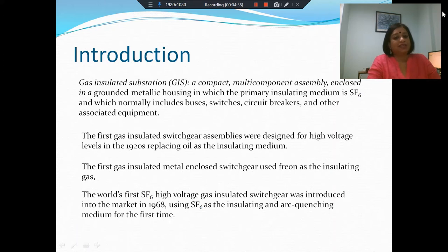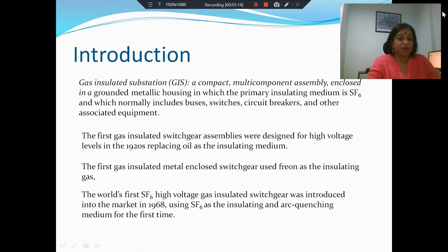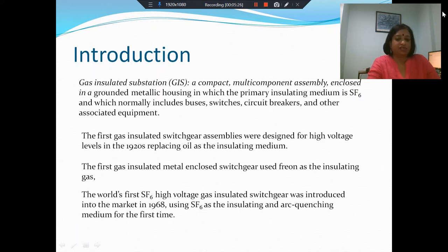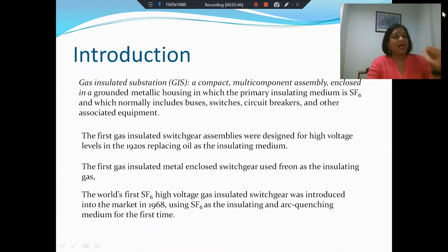The first gas insulated switchgear assemblies were designed for high voltage levels in the 1920s. Originally, circuit breakers had oil as the insulating medium; this oil was removed and replaced with gases. The first gas used for enclosed switchgear was Freon. The world's first SF6 high voltage gas insulated switchgear was introduced to the market in 1968. SF6 was chosen because it has high dielectric breakdown strength and, importantly for circuit breakers, good arc quenching properties. Only then did it come to be used in gas insulated substations.